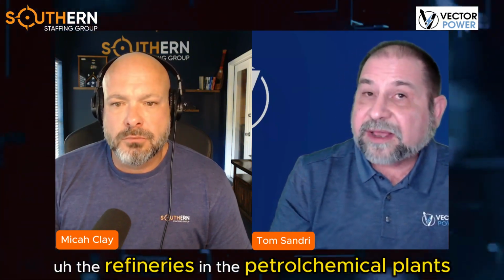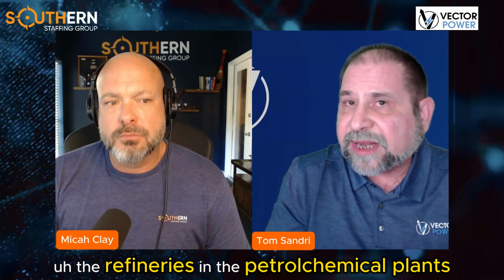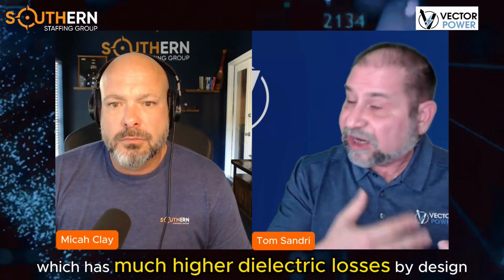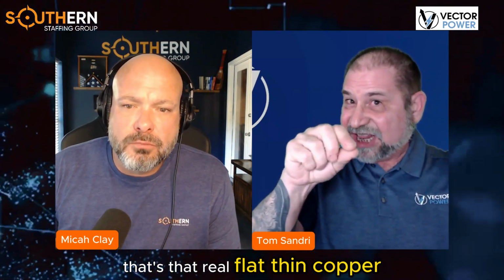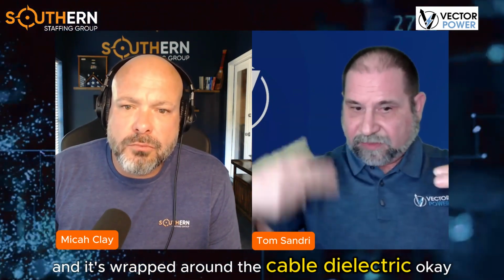Big industrial and commercial facilities, refineries, petrochemical plants, pulp mills, and so forth, tend to use a cable with a dielectric made of ethylene propylene rubber, or EPR, which has much higher dielectric losses by design than a polyethylene cable. Also, the shields they use tend to be ribbon or tape shields, that flat, thin copper wrapped around the cable dielectric, creating overlapping layers.